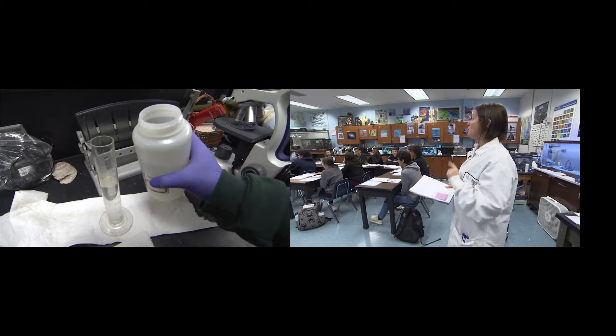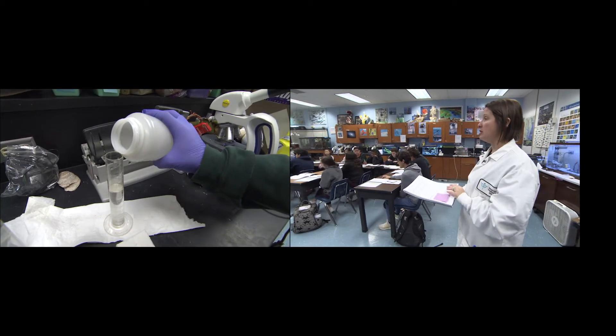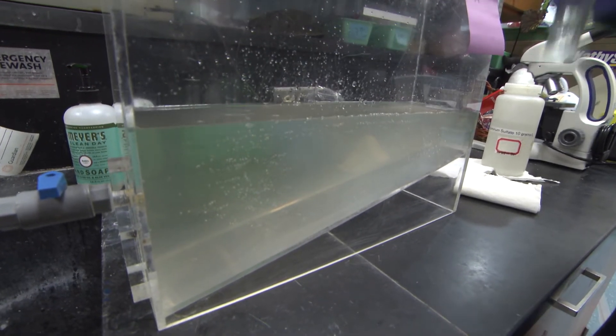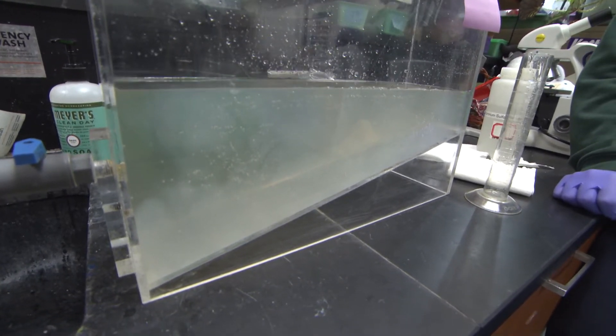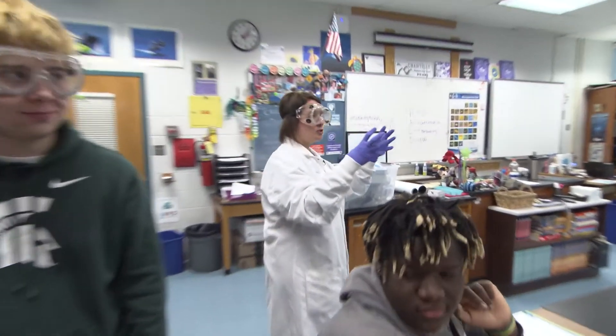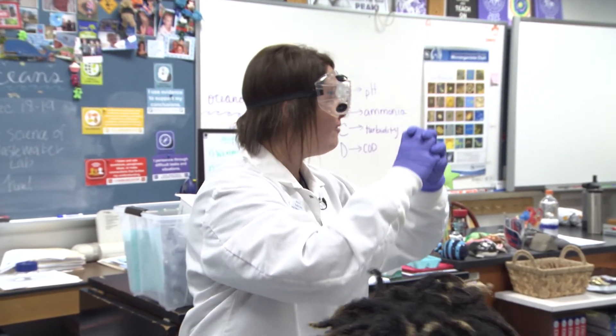We're going to go ahead and put the aluminum sulfate into our sedimentation tank so that this process can get started. It's a chemical reaction that's occurring — the aluminum sulfate is going to clump to the bacteria, and then the bacteria are going to get really heavy and fall to the bottom. At the wastewater treatment plant, water settles in these tanks for six to eight hours. Settled solids are sent back to the beginning of the treatment process where they are treated all over again.